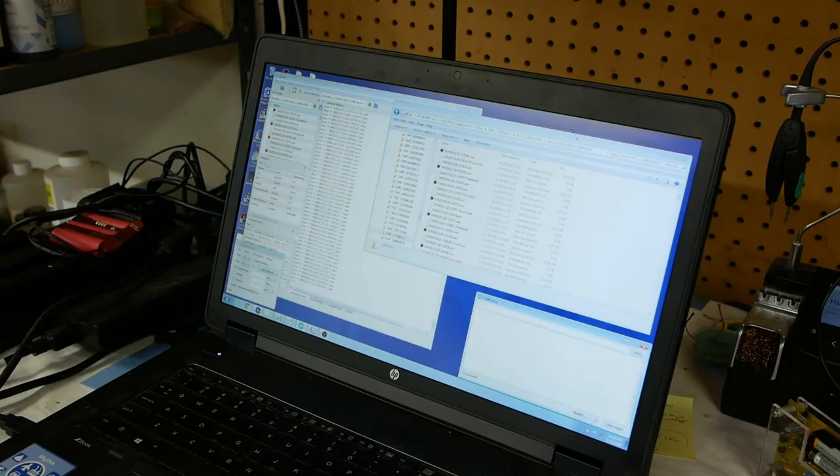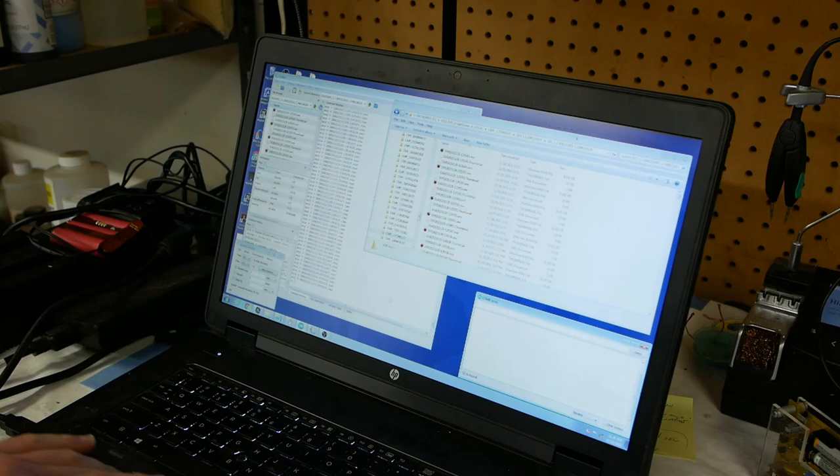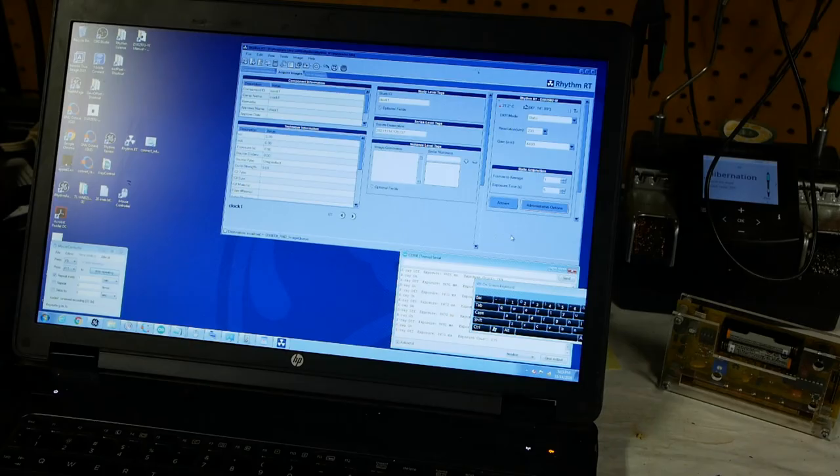The software that interfaces with the digital X-ray sensor is surprisingly difficult to use. It's kind of buggy and it's not extensible and it's kind of quirky in how it works. You might even say it's enterprise grade. But one of the quirks is that you can't really get images out of it programmatically. So the only way I could think of to automate it is to use a mouse control program and just record the mouse movements that I would use with the normal UI to get an image saved. This actually worked pretty well. It's a little hokey, but it did work.